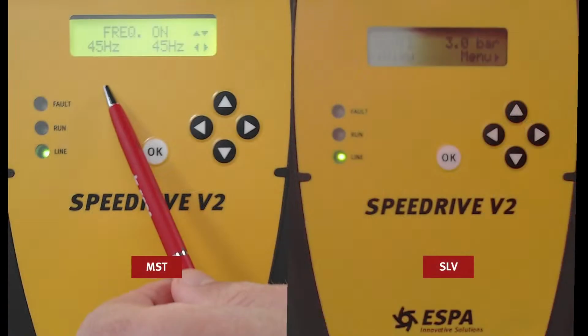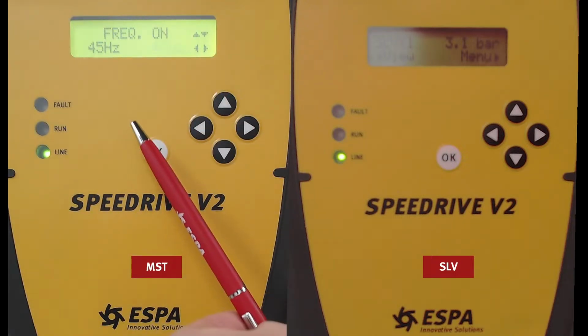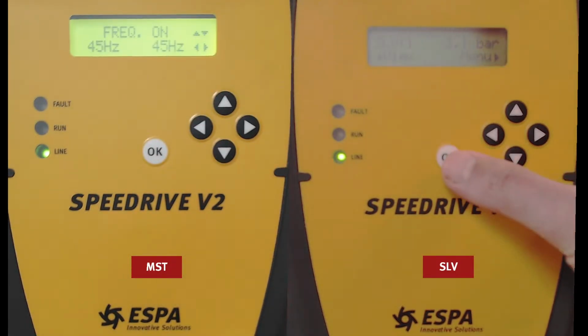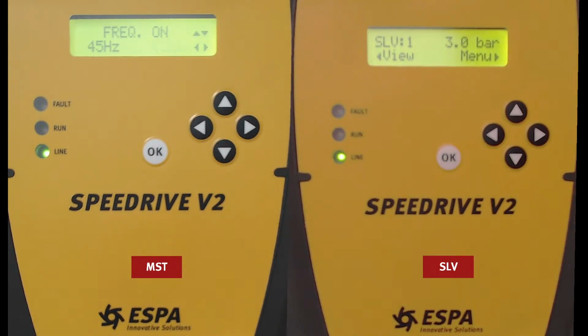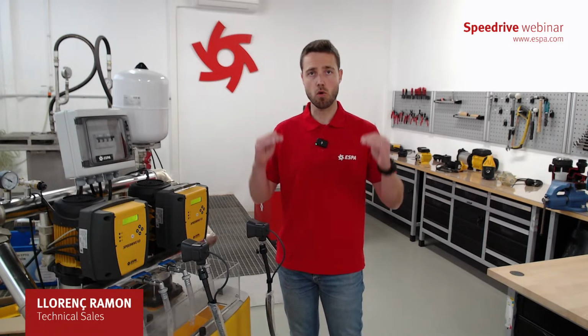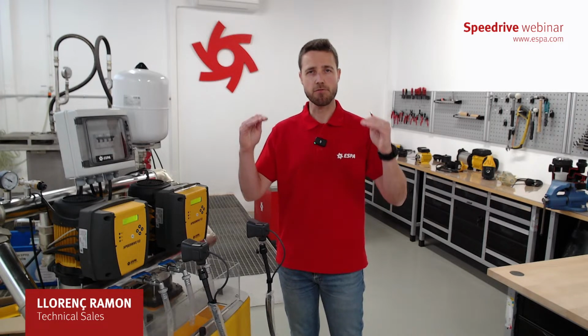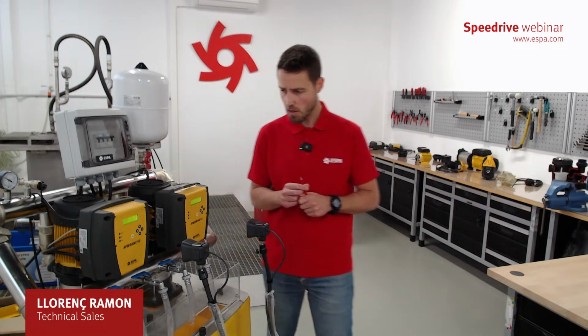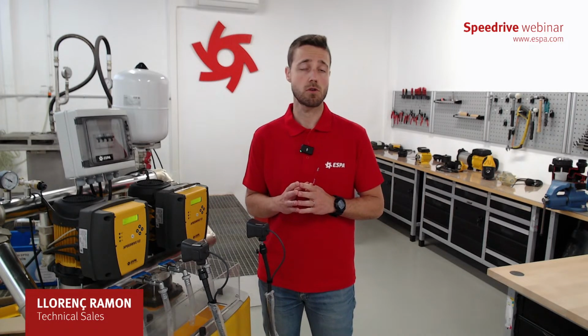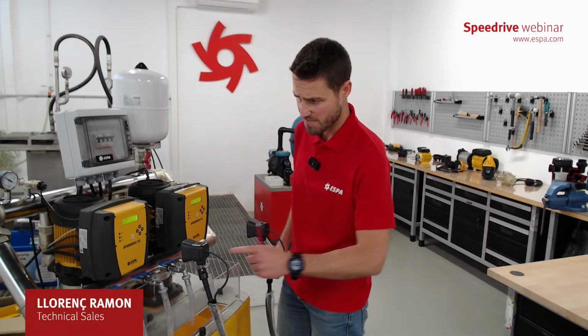So what's the meaning of 45 Hertz? That one pump will go maximum at 45 Hertz before starting the slave number 1, 2 or 3. So if we cannot maintain the pressure, at 45 Hertz we'll start the second pump, and both pumps will balance the system, the pressure. And once both pumps arrive at 45 Hertz, then from there it will increase, if necessary, up to 50 Hertz, but just in the last scenario. So with this solution, normally we will never reach, or almost never, the maximum speed of the pumps, so we can prevent them from premature damage. Let's continue.